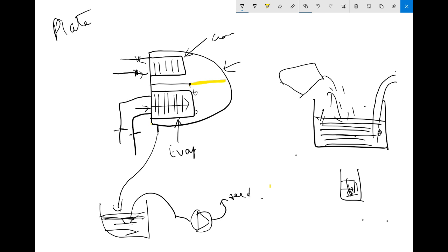Now about the demister, which I had not explained earlier. For plate type, you have the demister in this manner. The yellow color which I have shown is the demister. You will have to remove this manually, bring it outside and wash it. It's more than enough. If you feel it is very dirty, again you can do the same thing, put it in chemical like how we have put in plates. You can keep it for some time, and then wash it again, rinse it.